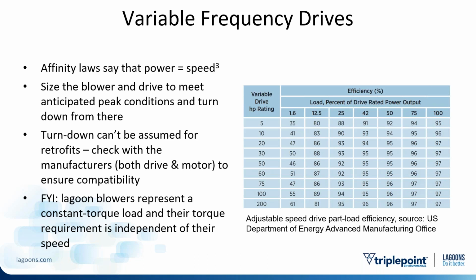But you don't want to size for peak condition and then run in that condition, because you're probably going to be using a lot more energy than you need to. If your system's sized for peak day or peak hour, your average daily flow is going to be a good bit less than that, and it's important that you turn down your blowers to match your daily flow to avoid spending extra money on energy.